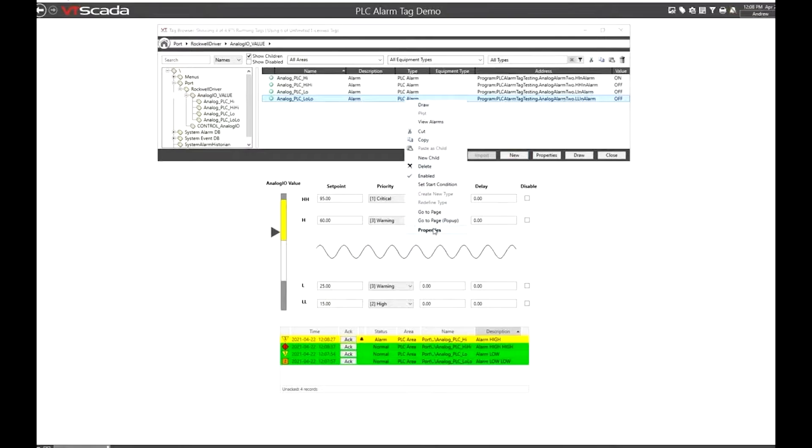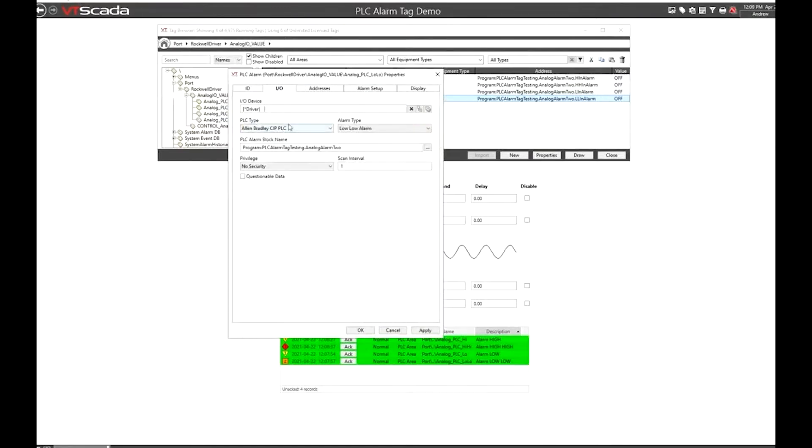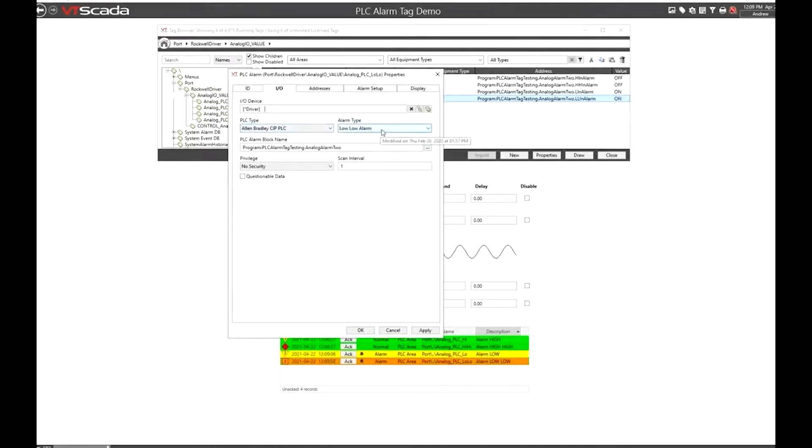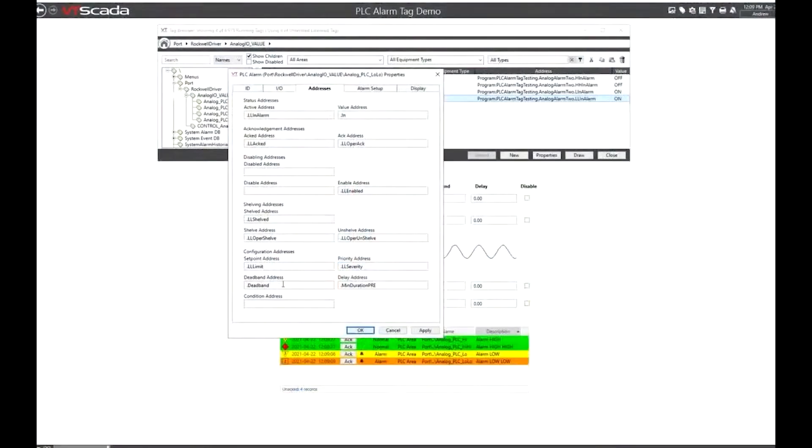I'll show you what the configuration of one of these tags looks like. We're hooked up to the driver where we have selected that we're using an Allen Bradley CIP PLC. I've selected the alarm type to be a low low alarm and I've provided the alarm block. The addressing in that PLC comes sort of pre-canned and we're just tapping into those predetermined addresses for the alarm status whether it's on or off, acknowledged, disabled, or shelved, and some configuration as well.